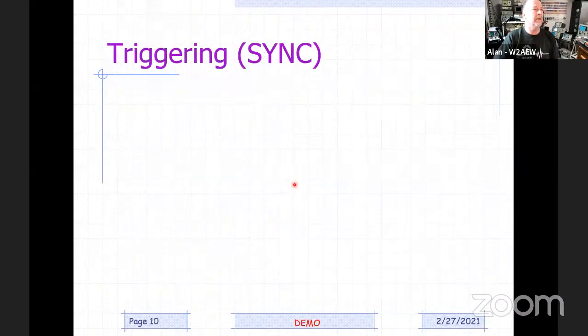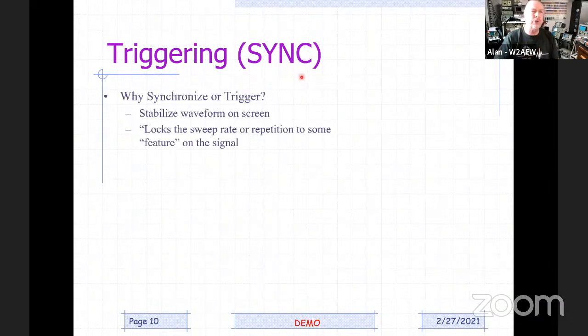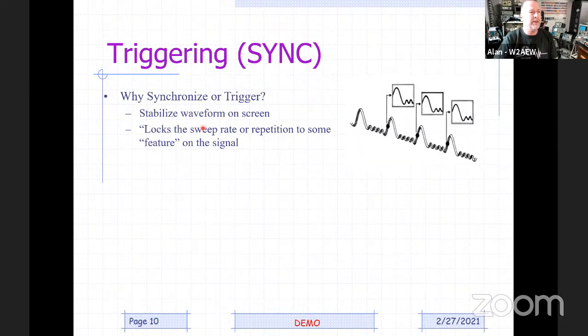Okay. So let's talk about triggering. Again, on the recurrent sweep scopes, it's called sync. Why do we want to trigger or synchronize? We want to stabilize that waveform on the screen. What that does is you're trying to lock the sweep to some feature on a repetitive waveform, so that we always start the sweep at the same point. So as you get multiple sweeps, the waveform overlays on top of each other, and you get a nice stable waveform to look at, like the background behind Pat there.